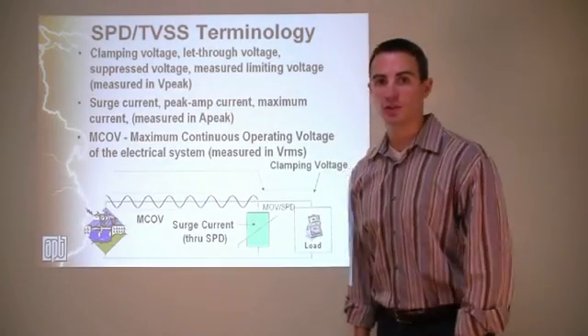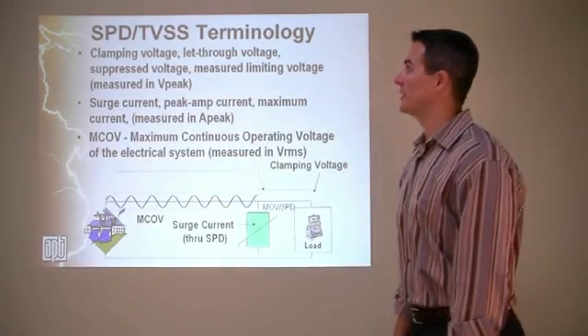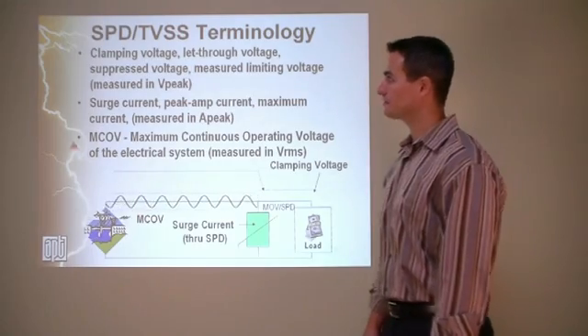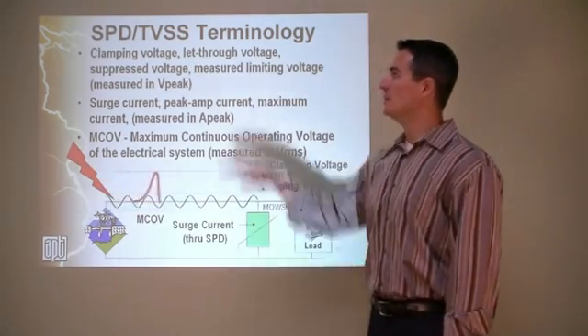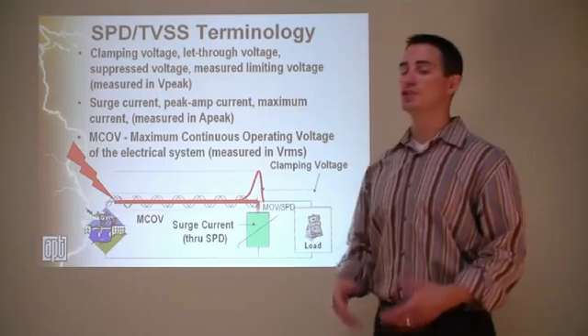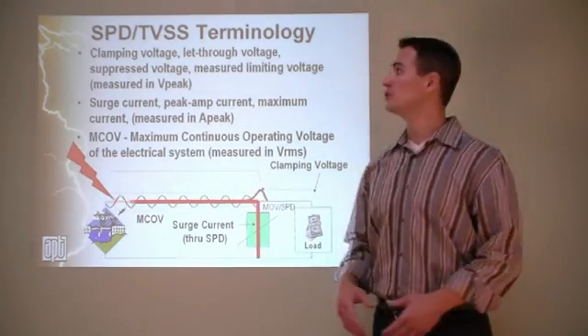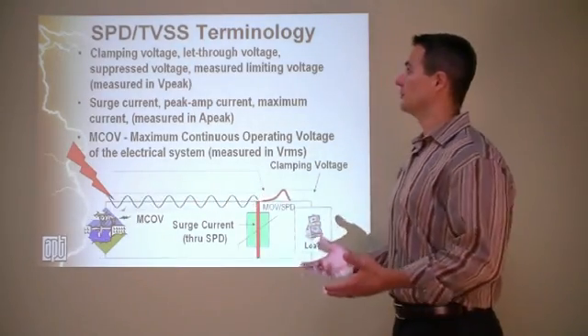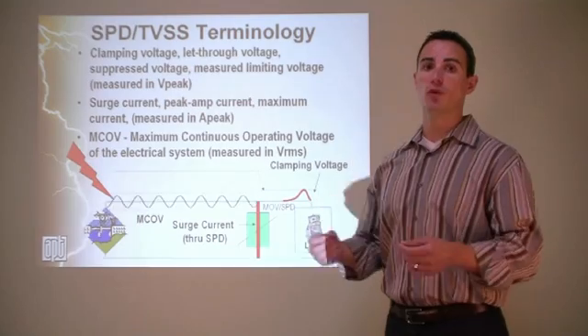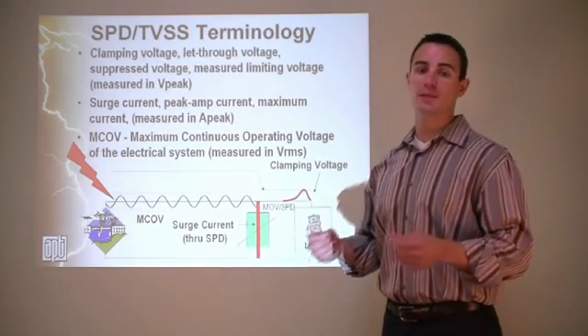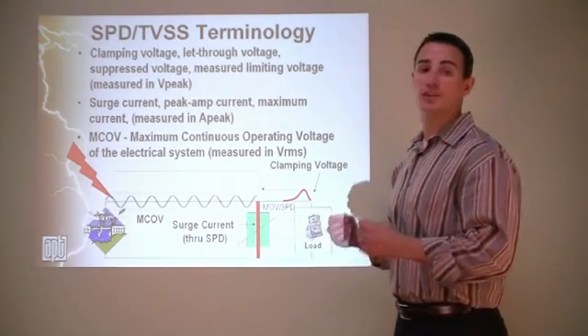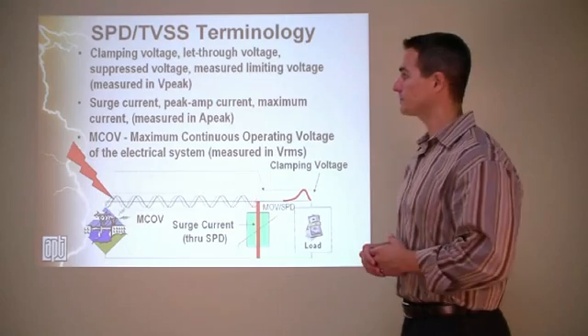In this module we're going to talk about basic SPD terminology. Clamping voltage is also known as let-through voltage, suppressed voltage, or measured limiting voltage. It's measured in V-peak, and it's the voltage that the SPD actually allows into the circuit.